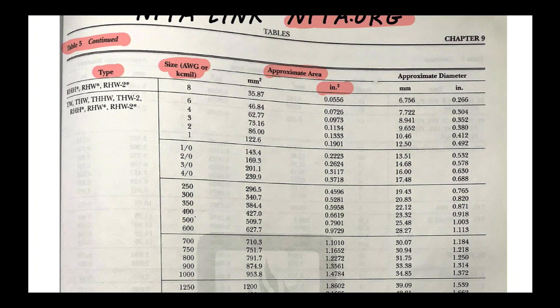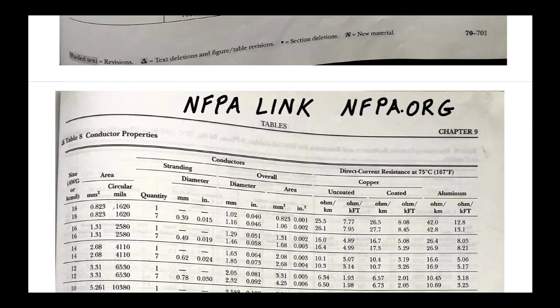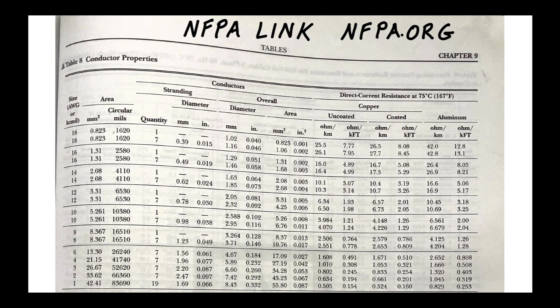The next table we're going to look at is Table 8, called 'Conductor Properties.' It's a very busy table. I highly recommend checking out the NFPA link at nfpa.org. The first thing is to look at this table and not go too nuts — let's look at the first column, which talks about the size in AWG or kcmil.